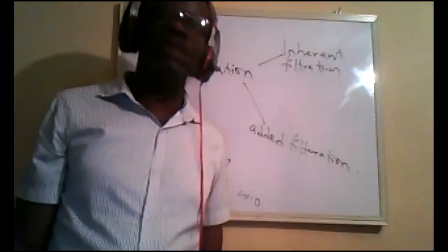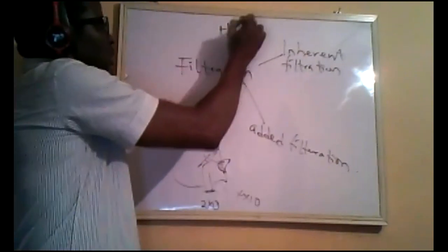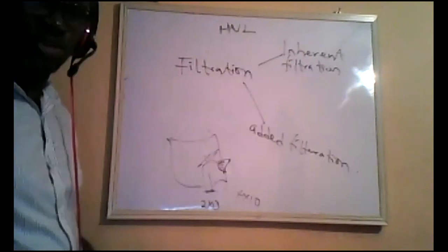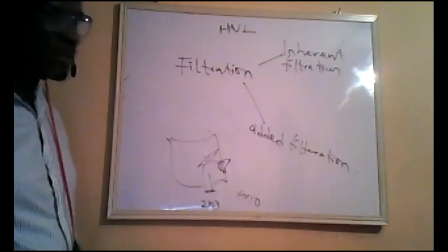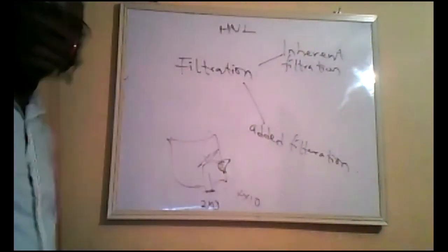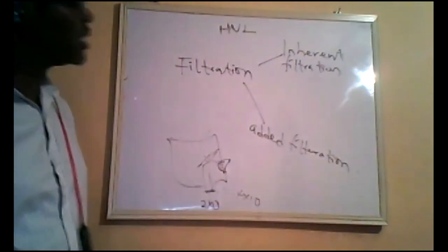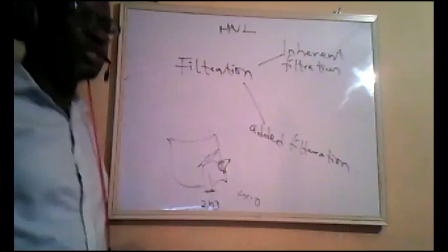In their center, they didn't know that there wasn't any filter inside the X-ray machine. It was when they were carrying out quality assurance, QA, and they started the HVL test, the half value layer test, that they discovered the values they were getting were very, very small compared to the values they should get for a particular range of energies. Then when they opened the X-ray, lo and behold, there wasn't any filter. So filter is very, very important so that we don't unnecessarily dose our patients.